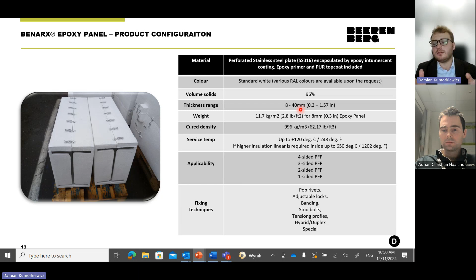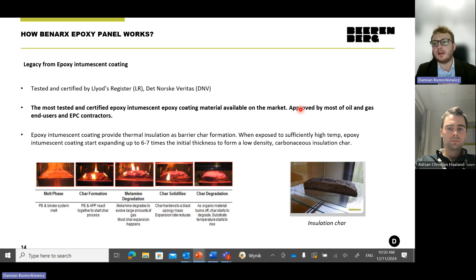How does our panel work? Basically, it works in the same manner as wet applied epoxy intumescent coating on a metallic substrate. When in contact with fire, it will start swelling and expanding up to 6-7 times its original dry thickness, creating a black insulating char around the metallic substrate to protect it against hydrocarbon fire.